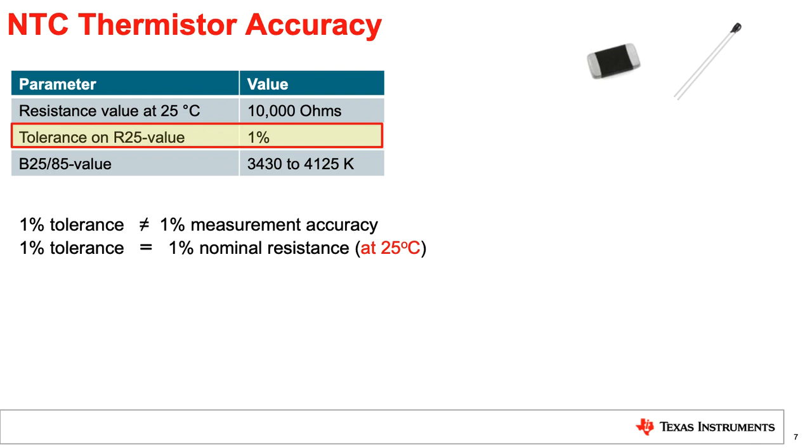Where the misconception usually comes from is how to interpret the tolerance in the NTC's data sheet. The assumption is that a 1% tolerance translates to a 1% measurement accuracy. 1% simply refers to the expected variability in resistance. So for a 10k NTC, it could be plus or minus 100 ohms. How much error that translates to will depend upon the actual temperature-resistance relationship for that thermistor. It's important to note that 1% tolerance in the resistance is only defined at 25C and could vary across temperature.